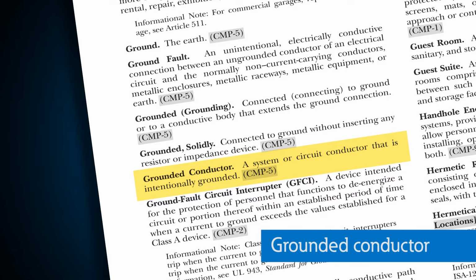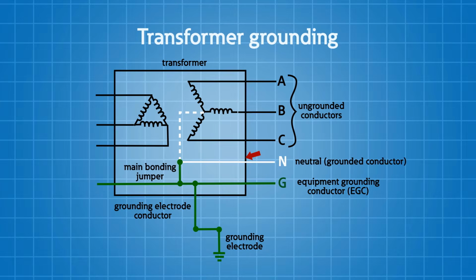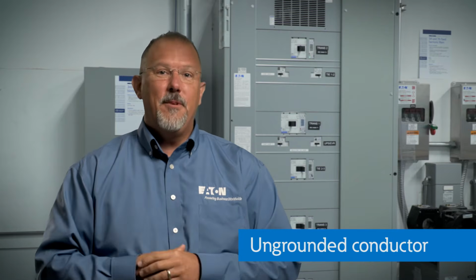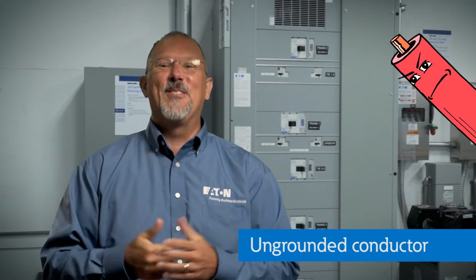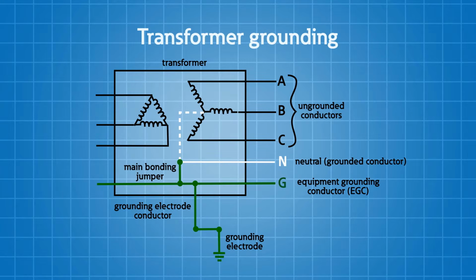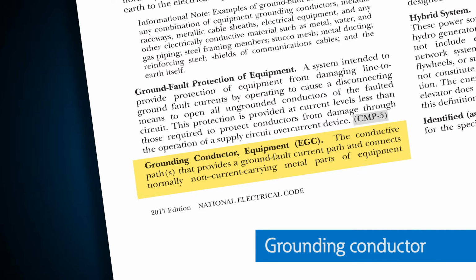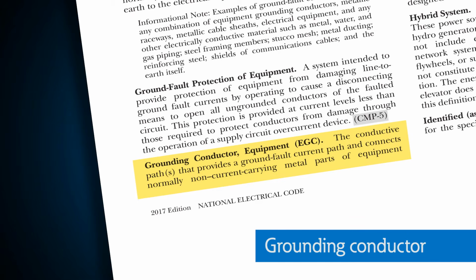All right, so now we're going to talk about the grounded conductor. This is the system or circuit conductor that is intentionally connected to the earth at that one point. We usually refer to this as the neutral. And its ugly brother, the ungrounded conductor, is a circuit conductor that is not intentionally connected to the earth. So this is usually your phase conductors. Your grounding conductor. I know we're saying a lot of terms here with grounded conductor, ungrounded conductor. Now we're going to talk about the grounding conductor.